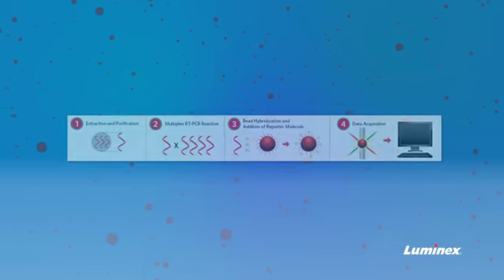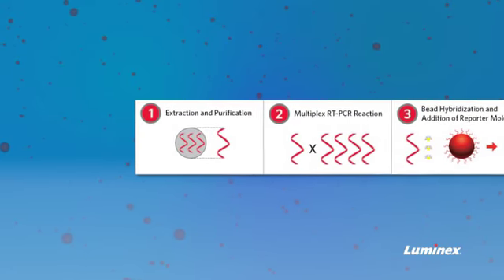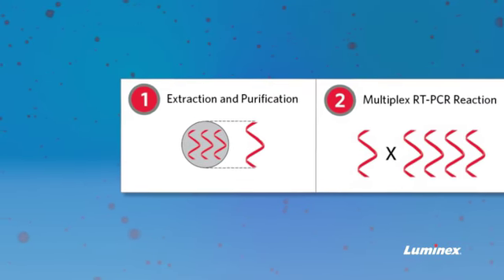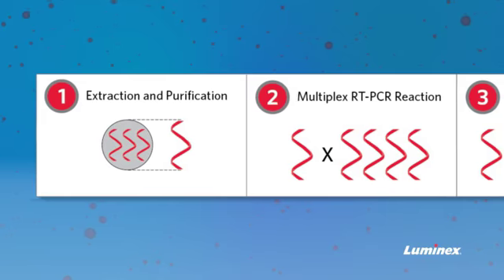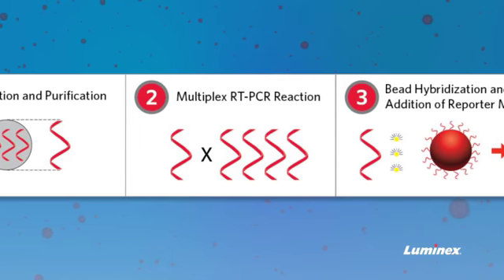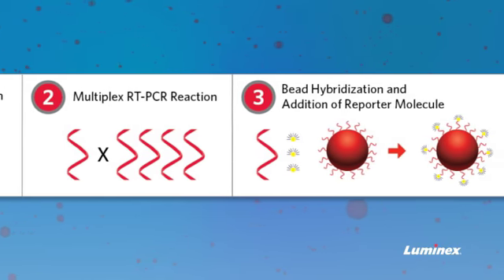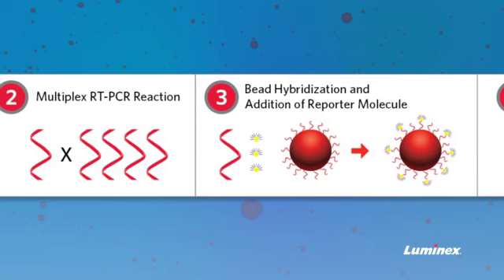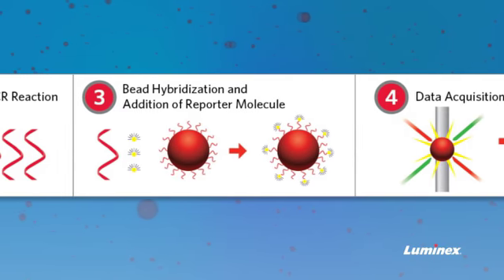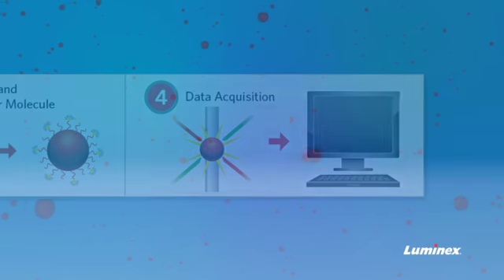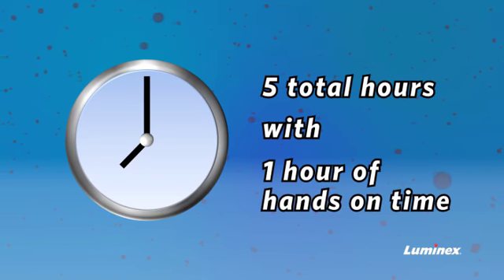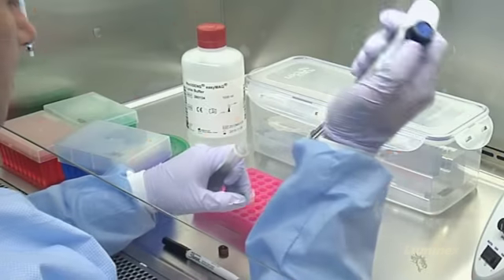In this four-stage process, the nucleic acid is extracted from the specimen and multiplexed in an RT-PCR reaction. It then goes through a bead hybridization where the reporter dye molecule is added so that the instrument can acquire the results. The process takes less than five hours for 24 samples with total hands-on time of about one hour.